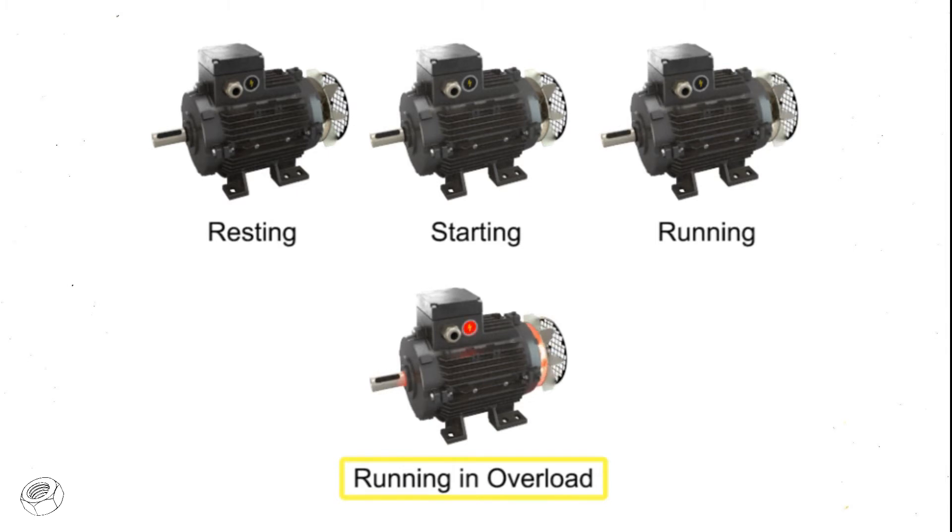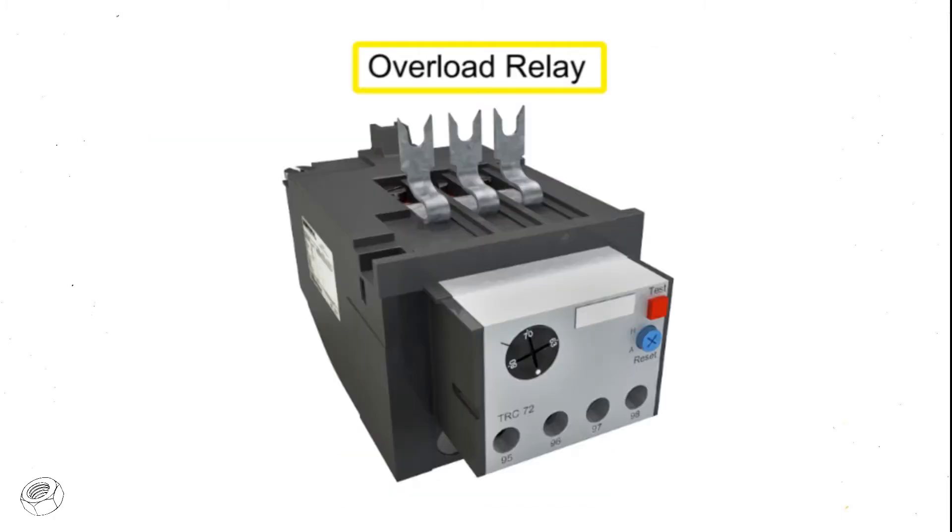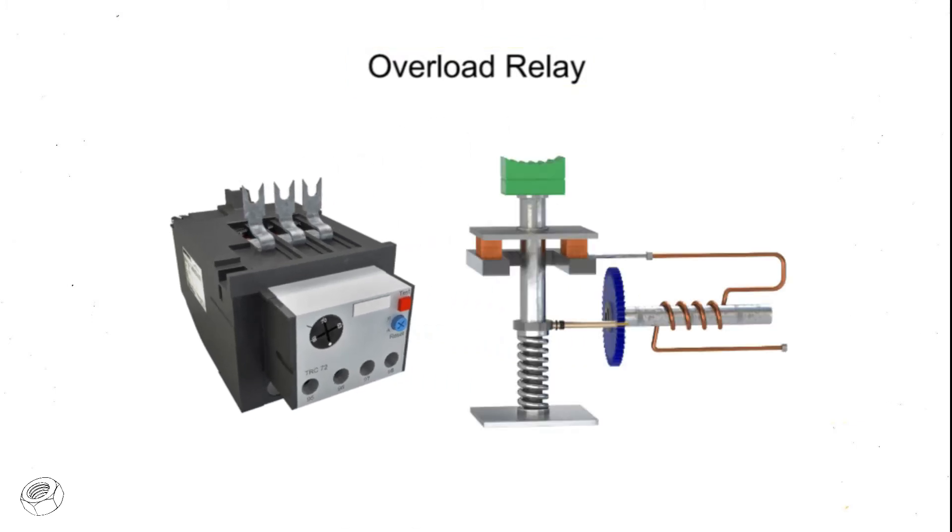To protect motors from running in overload, manufacturers typically protect their products with an overload relay connected to the motor starter. When an overload relay trips, it opens contacts within the control circuit stopping the motor.